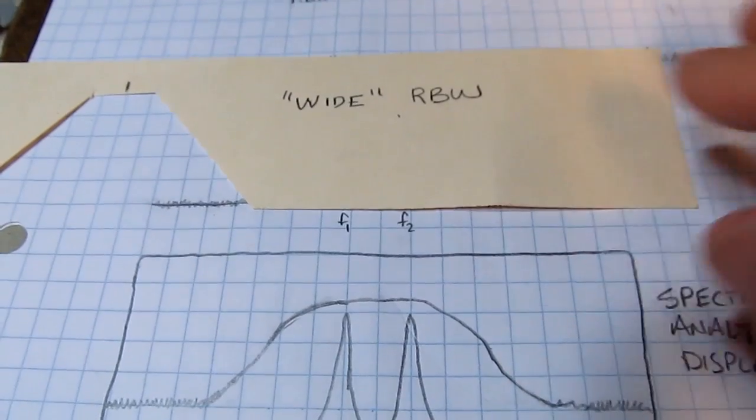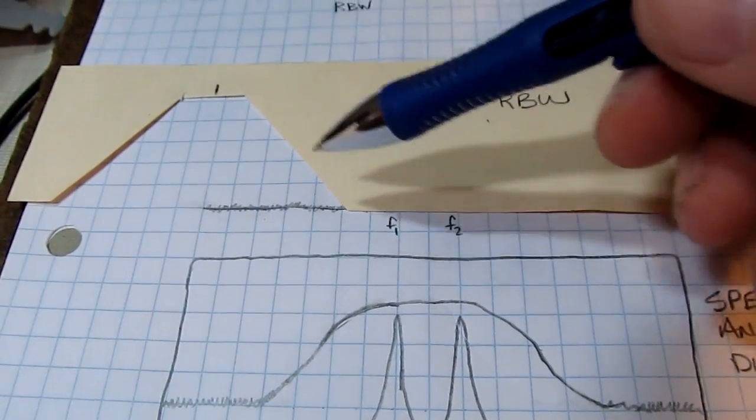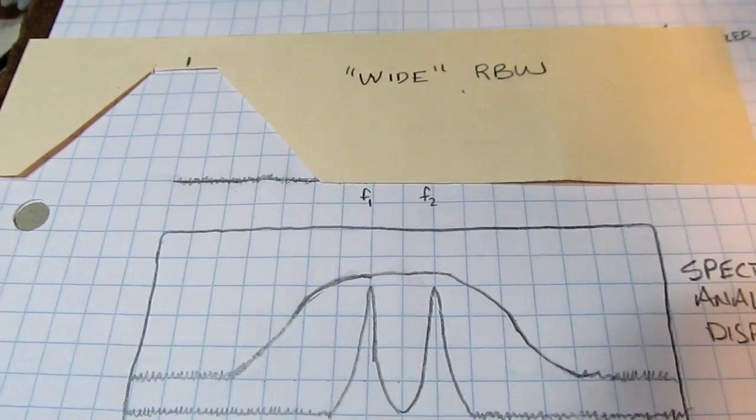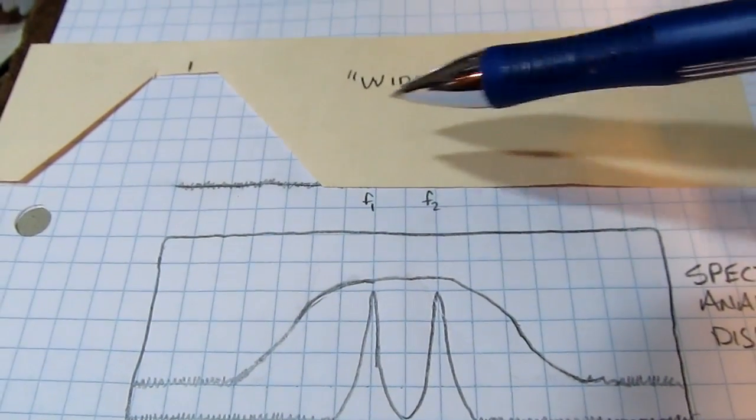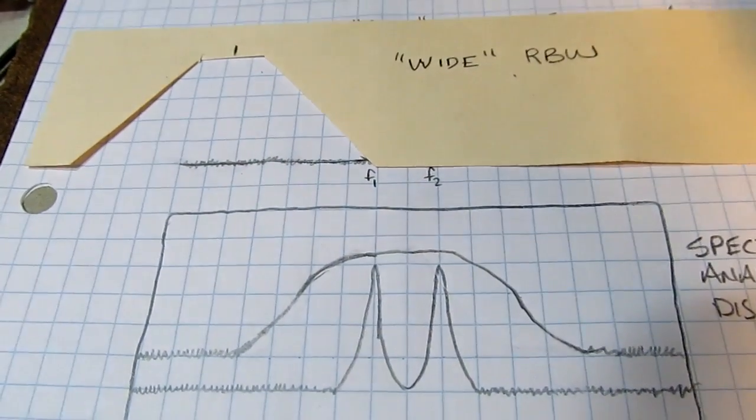Effectively we're going to sweep those things through the resolution bandwidth filter. Now let's say we had a wide resolution bandwidth filter. As we sweep this through, the power that's measured in this filter is going to be plotted out on the spectrum analyzer display. For the wide filter as we slide this through, up to this point we haven't seen any of those signals yet. So we're just plotting out essentially the noise or the noise floor of the analyzer.